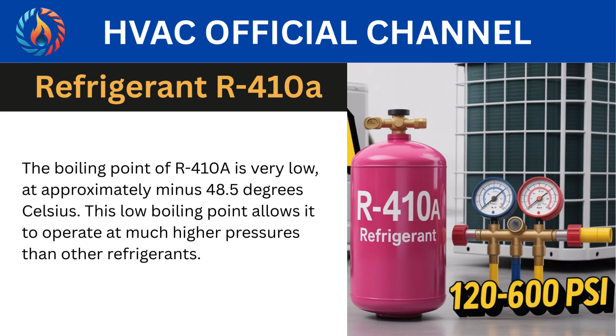R-410A pressure guide. Standing pressure, 225 pounds per square inch to 250 pounds per square inch, varies with ambient temperature. Suction, low side pressure, 120 pounds per square inch to 150 pounds per square inch. Discharge, high side pressure, 450 pounds per square inch to 600 pounds per square inch.